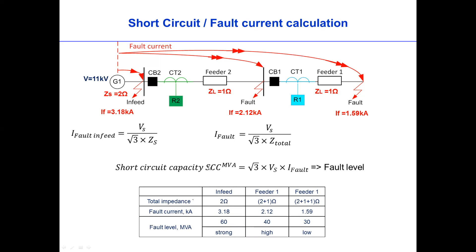If we look at the summary of these fault levels against the impedances at the fault level, at the infeed, the total fault current is 3.18 kilo amp. At feeder two, it is 2.12 kilo amp, which is this one.